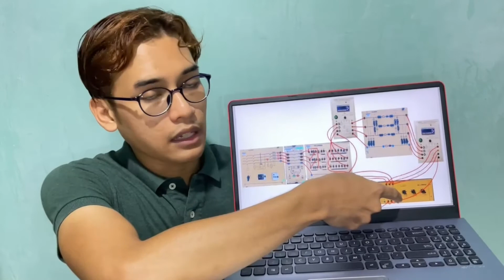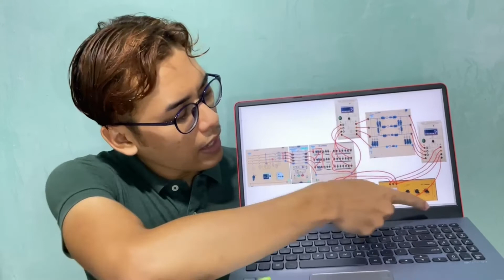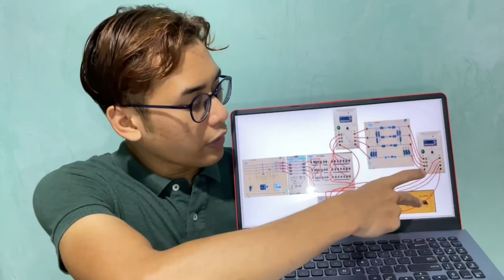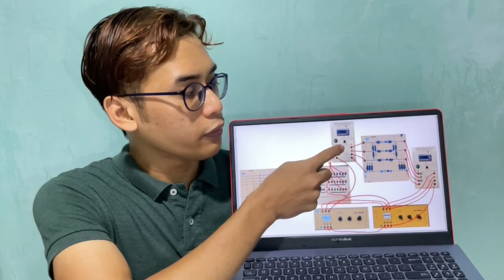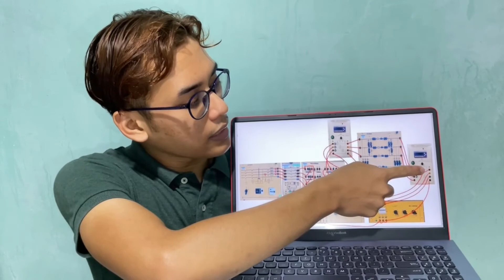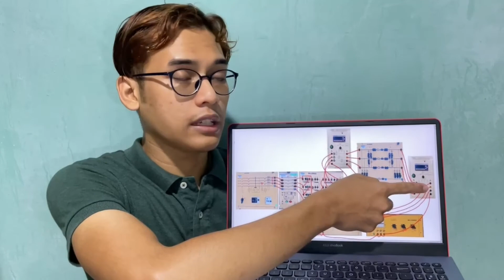Now we start with table 8.5. This is the resistive load and this is the capacitive load. For the resistive load we change the value to level 3, and for the capacitive load we change the value to level 1. After that, we find the values of U1, I1, P1, and Q1 at the first 3-phase digital meter for the beginning line, and U2, I2, and cos theta 2 at the second meter for the end line.